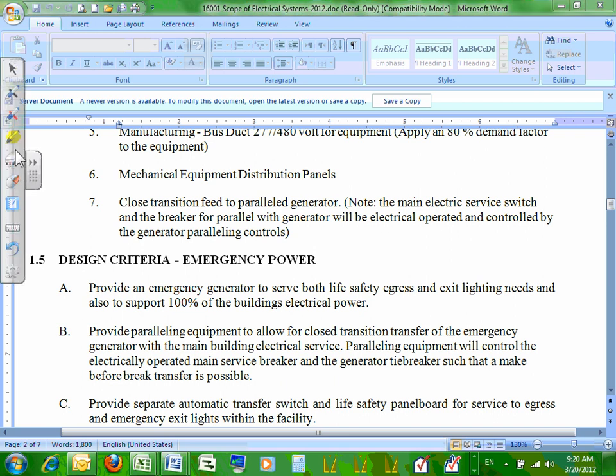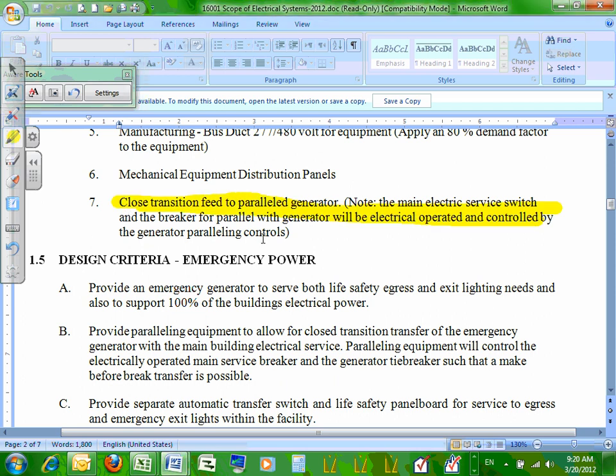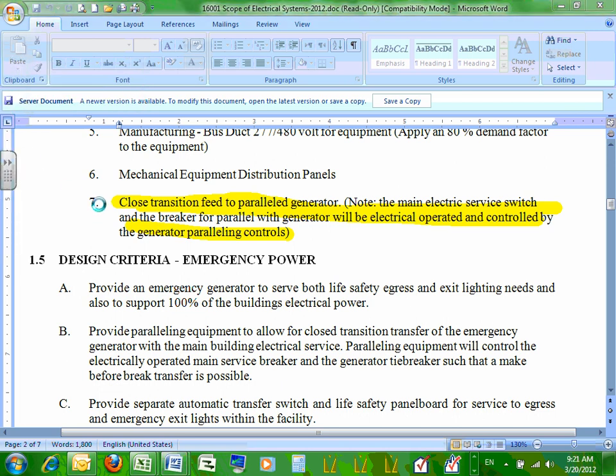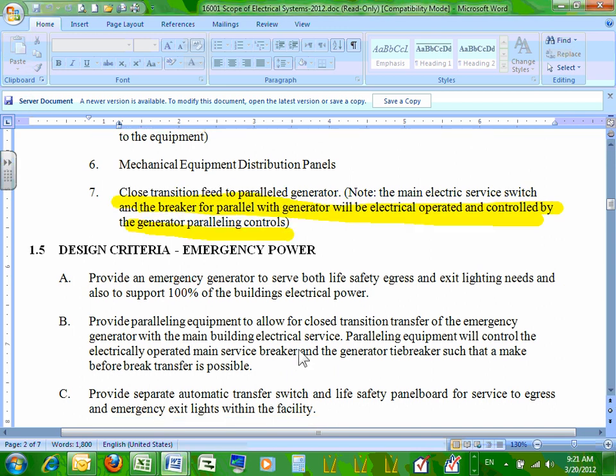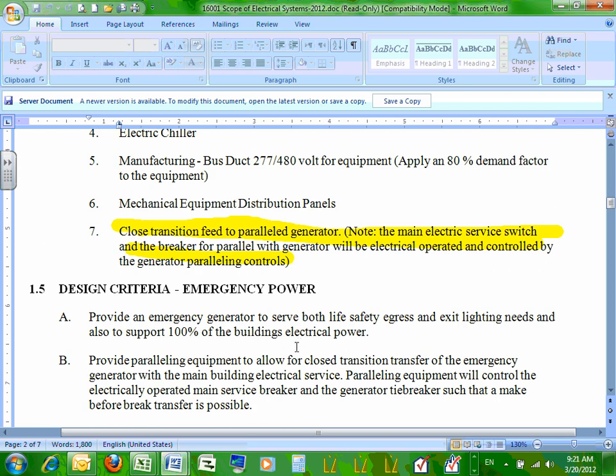That's all right. Your commercial project, you had an automatic transfer switch that went to the generator, and it went to the utility feed. So at some point we have an automatic transfer switch. It gets a generator source, and it gets a normal source, and then here's my load. That's my emergency power. That's my ATS, and that'll come up again a little bit later because I need an ATS for my required life safety loads in this building. So I'll have an ATS for that.